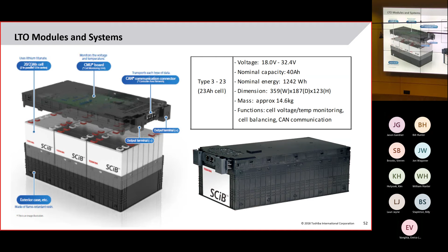If you're UL 1973 listed specifically, lithium-ion batteries need to be monitored at the cell level - current, voltage, and temperature, with temperature able to be done at the jar level. All three parameters need to be reported in some way for each cell within the string, then from the string to the building management system. That applies to all lithium-ion batteries.